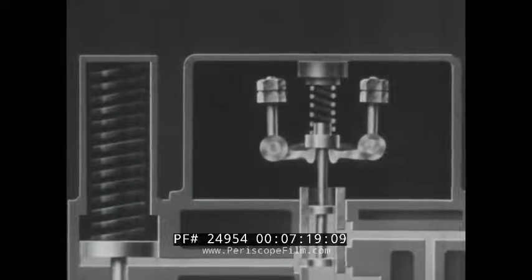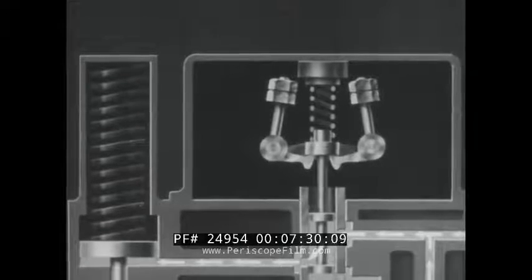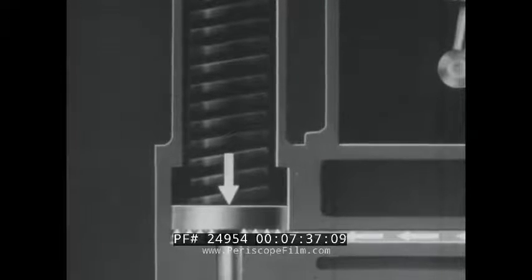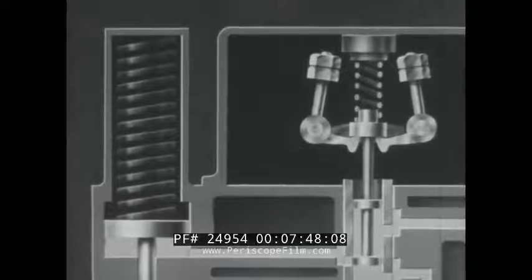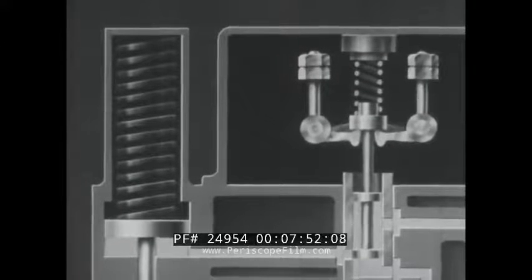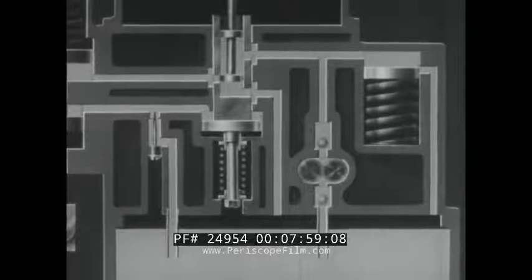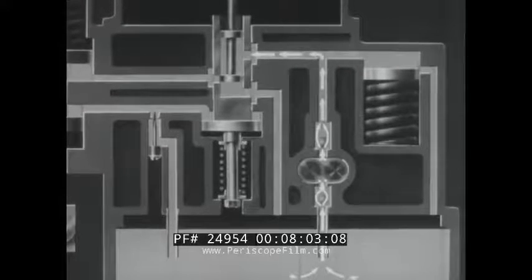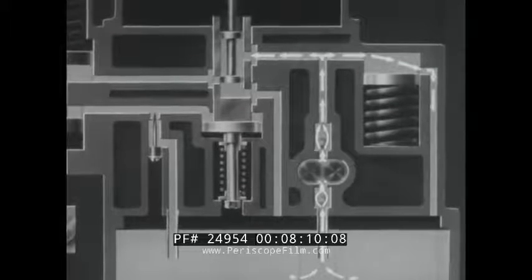If the load increases, the engine slows down and the flyweights move inward. This lowers the pilot valve plunger, allowing oil to flow through the pilot valve chamber to the power cylinder. This oil, supplied by a pump, is under pressure sufficiently high to overcome the pressure of the power spring. The power piston moves upward, increasing the amount of fuel injected into the cylinders. Once again, as the speed returns to the set rate, the flyweights resume their central position. The gear pump, which supplies the high-pressure oil, is driven from the governor drive shaft and takes suction from the governor oil sump. A spring-loaded accumulator maintains a constant head of oil and allows excess oil to return to the sump.